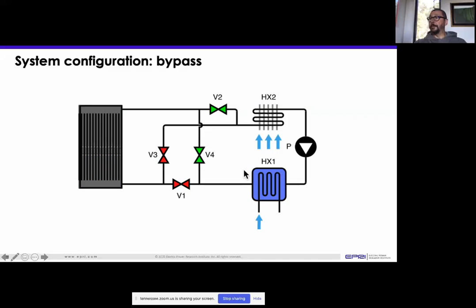There may be cases where your storage is discharged and you just want to bypass it, so again you operate some valves, and now you're using your heat pump to provide cool to the heat exchanger directly, cooling down the heat medium and the air in your house. This mode is basically just using your air conditioner normally.